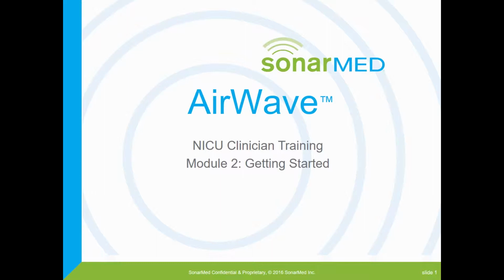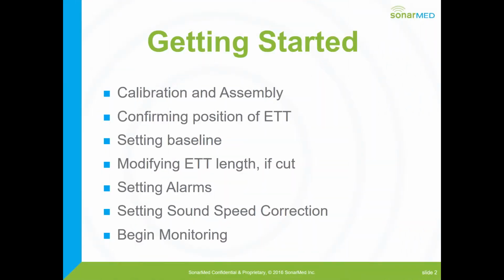So today we'll talk about calibration and assembly, how you put it together. We're going to talk about how you confirm the position of the endotracheal tube. How do you set baseline? If you've cut the endotracheal tube, which very often is done in the neonatal intensive care, how to modify the length on the monitor. Setting alarms and setting them so that they count and they matter. Also setting sound speed correction if necessary, and then getting ready and beginning to monitor.